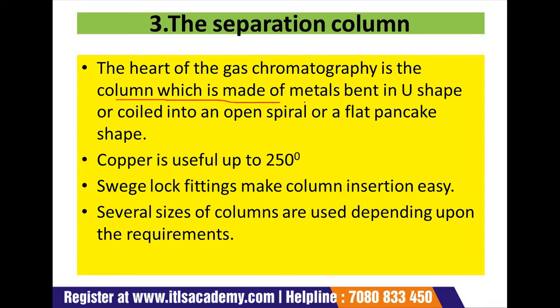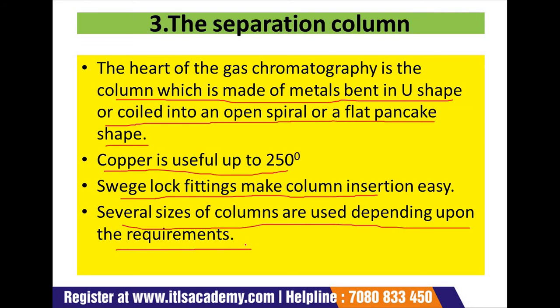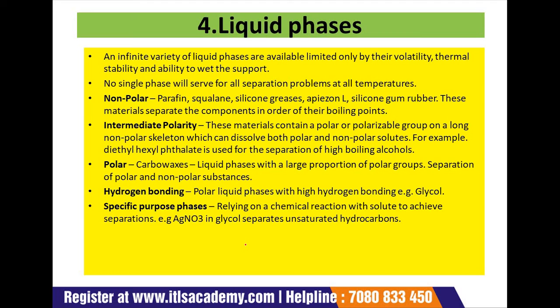The heart of the gas chromatography is the column, which is made of metal bent in a U-shape or coiled into an open spiral or flat pancake shape. Copper is used up to 250 degrees centigrade, and Swagelok fittings make column insertion easy. Different sizes of columns are used depending upon the requirements.